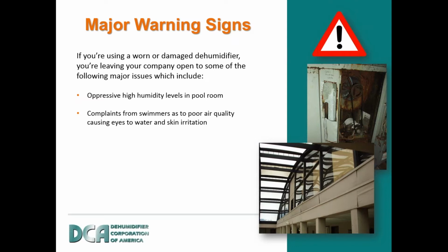These are normally keys that there is a problem. Now, if you're in a cold climate in the wintertime, you're going to see a lot of moisture building up on windows and any condensable metal surface. This is certainly another way to know that the system is not operating correctly. We talked about formation of mold and mildew anywhere in the pool room structure, and in any place that you see it it's going to be a problem.